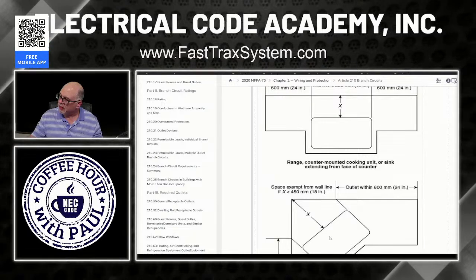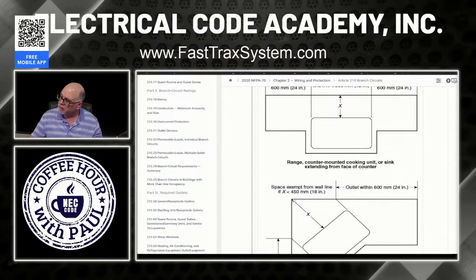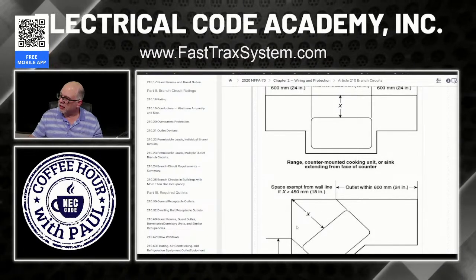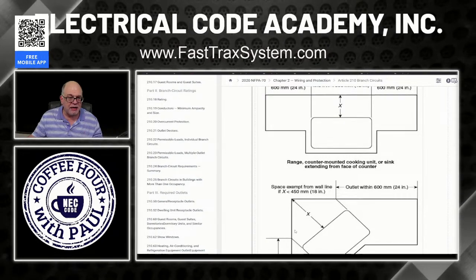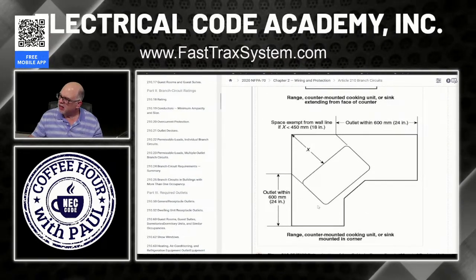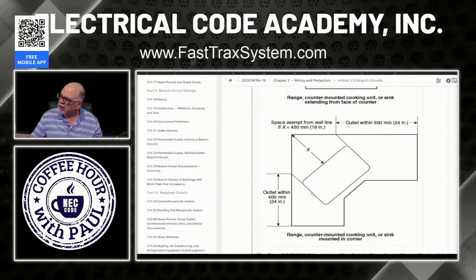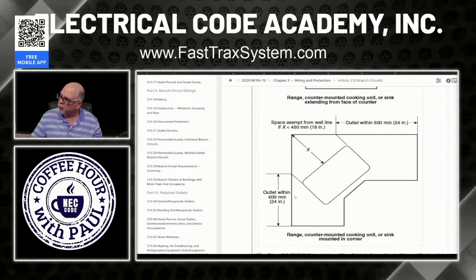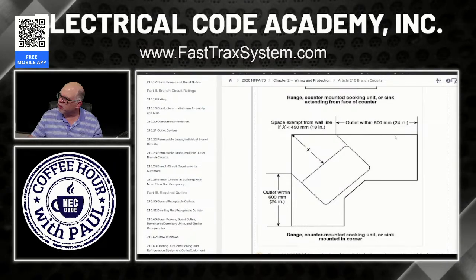Down here, same thing. If this space and a corner mounted one, if between here and the corner is less than 18 inches, then you can ignore this space. And the measurement starts by drawing an imaginary line. Let me bring this up here so you can see it. An imaginary line right here. See my mouse? Right here, draw a line back to the wall. And this is where your measurement starts, right from that contact point this way. Same on this side. Measurement starts this way.